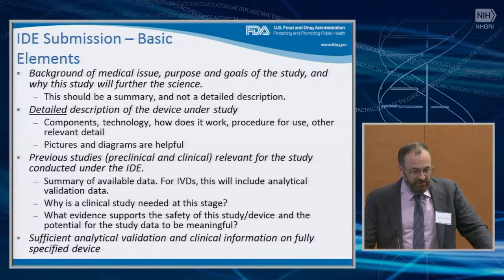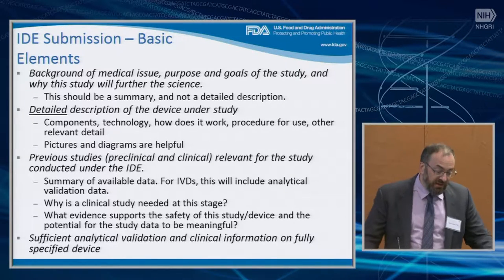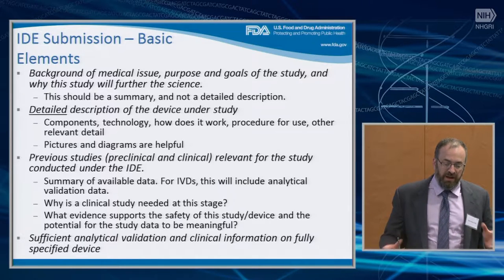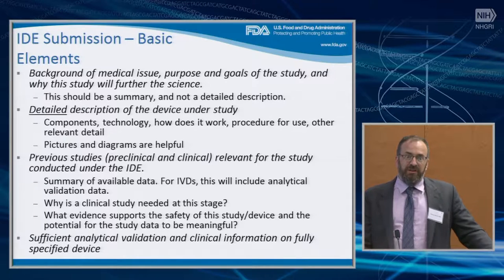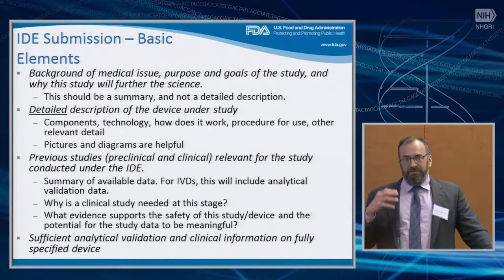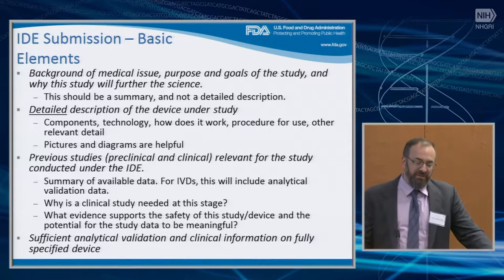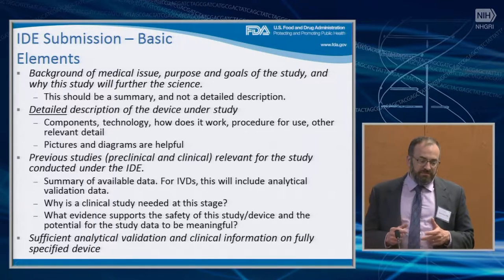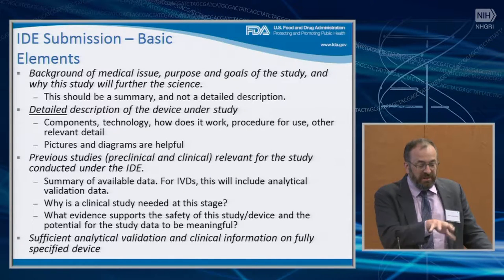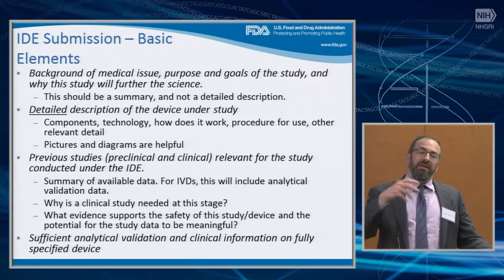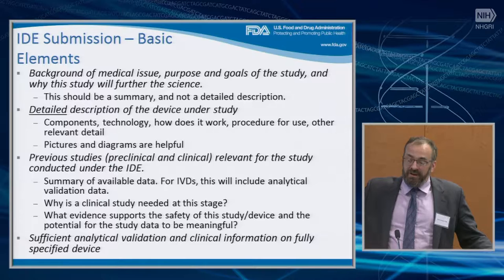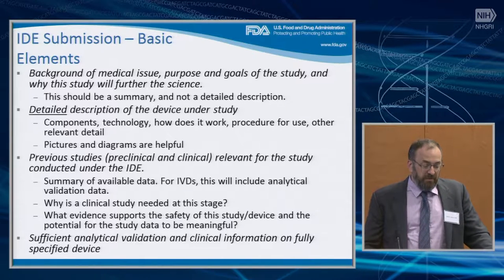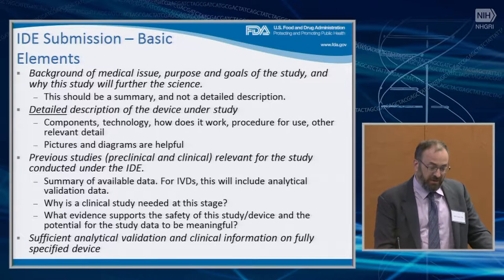The previous studies — preclinical and clinical — would include the analytical validation studies you've done and the evidence that's leading you to put this in a trial. Things that have been studied about the device or technology that aren't relevant to the study are not as important. We need enough analytical validation and information on the device you're going to use in the study. One of the challenges in genomics is that devices are changing rapidly, and there can be many modifications over the course of the study, so you have to consider those modifications.